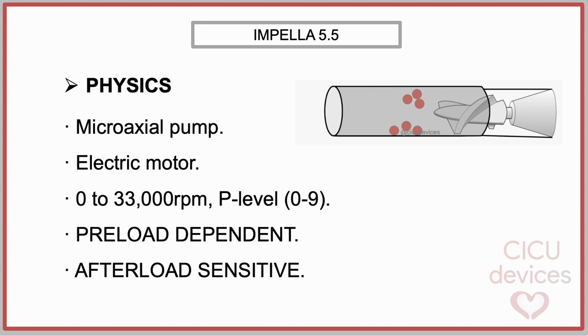The Impella 5.5 operates via a microaxial pump driven by an electric motor. Pump speed is measured in revolutions per minute and typically ranges from 0 to 33,000 revolutions per minute, depending on the performance level selected. Flow output is not fixed for each P level. Rather, it is preload dependent and sensitive to afterload.